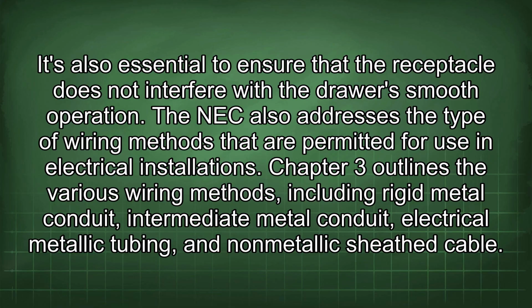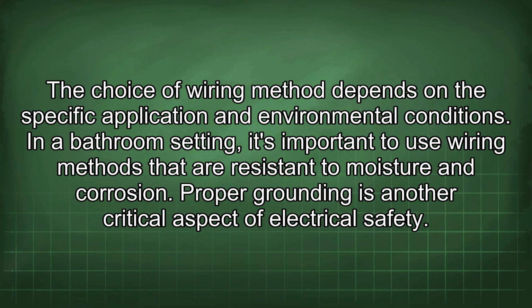The NEC also addresses the type of wiring methods that are permitted for use in electrical installations. Chapter 3 outlines the various wiring methods, including rigid metal conduit, intermediate metal conduit, electrical metallic tubing, and non-metallic sheathed cable. The choice of wiring method depends on the specific application and environmental conditions. In a bathroom setting, it's important to use wiring methods that are resistant to moisture and corrosion.